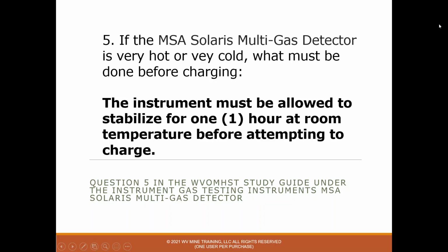Question 5, if the MSA Solaris multi-gas detector is very hot or very cold, what must be done before charging? And the answer is the instrument must be allowed to stabilize for 1 hour at room temperature before attempting to charge. I used to have this problem. I had a Solaris that I would use in training classes, and it would be just in my truck. And I usually just left it in there, and I'd say, well, I need to charge my detector, so I would go get it. My truck may be cold, and it would never charge, and it has to stabilize at room temperature, normal, what would be in your mine warehouse or bathhouse or in your house or whatever. But it does have to stabilize 1 hour at room temperature before you charge it.